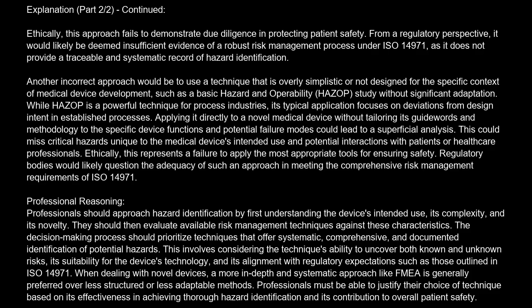Another incorrect approach would be to use a technique that is overly simplistic or not designed for the specific context of medical device development, such as a basic hazard and operability (HAZOP) study without significant adaptation. While HAZOP is a powerful technique for process industries, its typical application focuses on deviations from design intent in established processes. Applying it directly to a novel medical device, without tailoring its guide words and methodology to the specific device functions and potential failure modes, could lead to a superficial analysis. This could miss critical hazards unique to the medical device's intended use and potential interactions with patients or healthcare professionals. Ethically, this represents a failure to apply the most appropriate tools for ensuring safety.